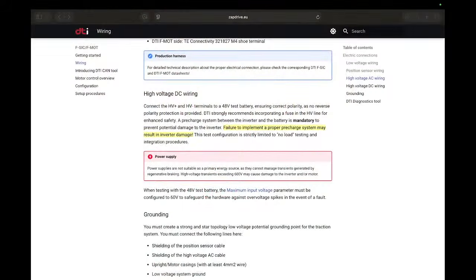Also need to mention that the inverter does not include any kind of pre-charge system inside, nor a discharge system. The inverter is capable of doing discharge by itself, but this is not really meant for an operational discharge, only for maintenance kind of discharge. It takes like 5 minutes to fully discharge the capacitance inside the inverter. So this is not meant for operational discharging, but only for maintenance purposes.